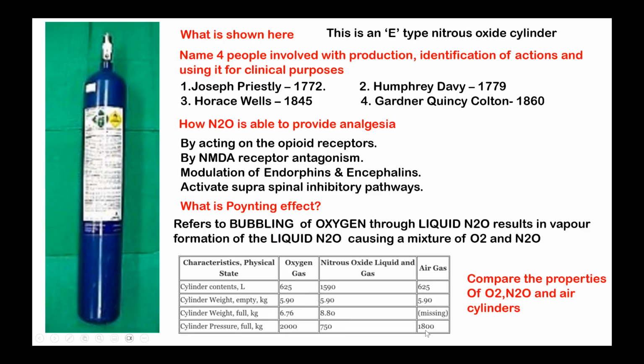It is about 750 for nitrous oxide, and the air cylinder is 1800. Please remember this value, because nowadays we are regularly using air in anesthesia, avoiding nitrous oxide. They may ask you the pressure inside a full air cylinder - it is slightly lesser than oxygen, but it is 1800.